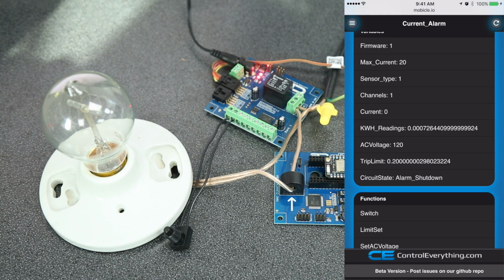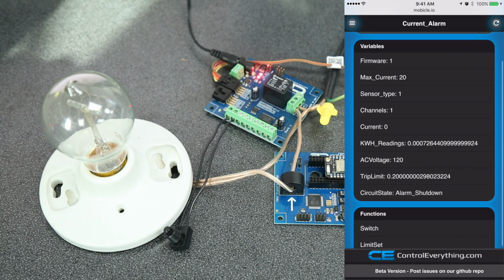Here we can see the variable trip limit. That is the current limit. So if we exceed that, the circuit shuts down. You'll see mine set to 0.2 or about 200 milliamps.